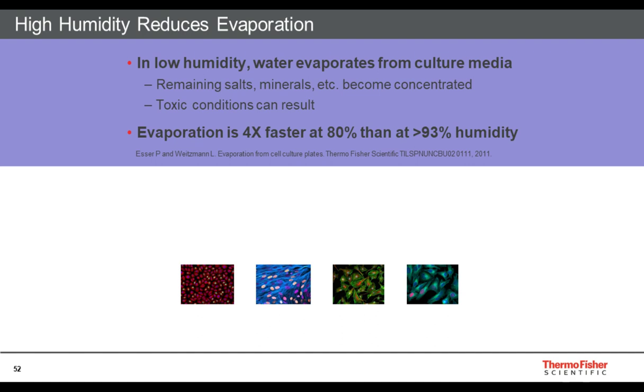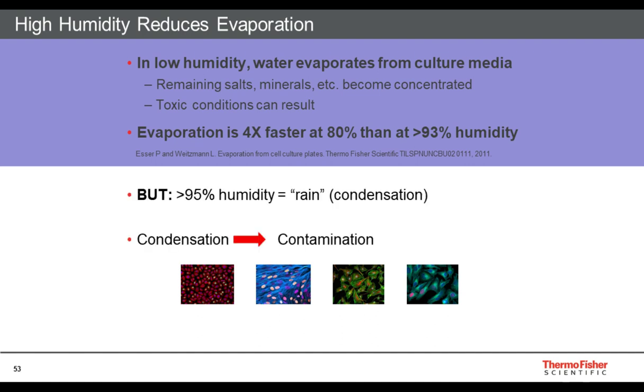The growth media that we use are precisely balanced for a reason. If the nutrients or test factors, the things that we're working with to stimulate the cells, become too concentrated, that can reach toxic concentration. It also turns out that evaporation is 4 times faster at 80% humidity than at 93% humidity or greater. So high humidity is a good thing, but as you approach 100% humidity, you get condensation. Essentially, 100% humidity is rain, right? Over about 95% humidity, you can see condensation in the incubator, where the water vapor collects and you see puddles or droplets of water.